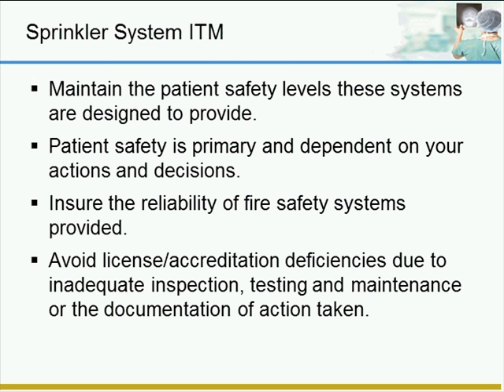Okay. Thank you, Jim. The previous slide was a nice segue into our discussion on sprinkler system inspection, testing, and maintenance, also known as ITM. At a minimum, all sprinkler systems should receive ITM at least once per year. Twice per year is better, and quarterly is the best. All healthcare facilities are required to maintain proper ITM documentation.